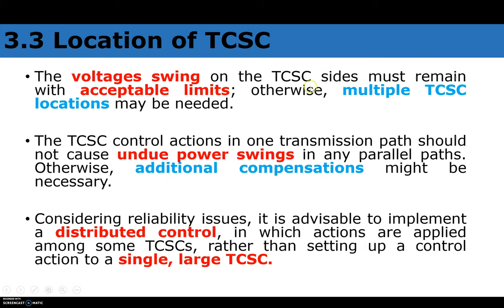The voltage swings on TCSC sides must remain within acceptable limits, because the power system must be operated within constraints including frequency and voltage constraints. If voltage swings exceed limits, multiple TCSC locations may be needed. Instead of one huge capacity TCSC at a single location, it is better to consider three or five locations, dividing that large capacity into multiple banks installed at multiple locations, which gives maximum satisfaction in power system operation.